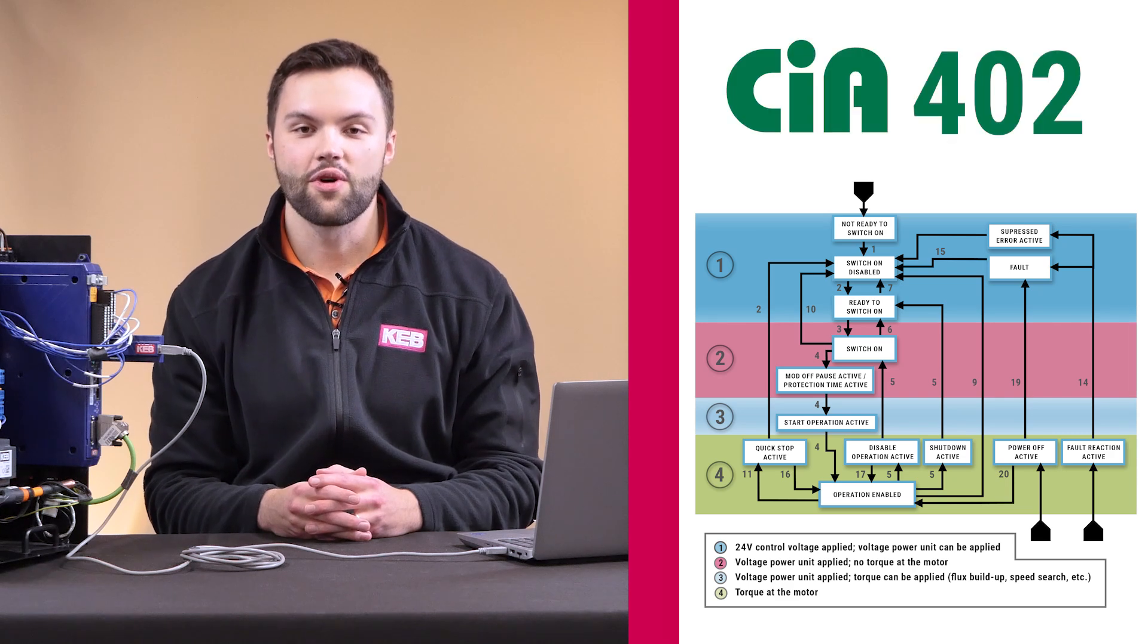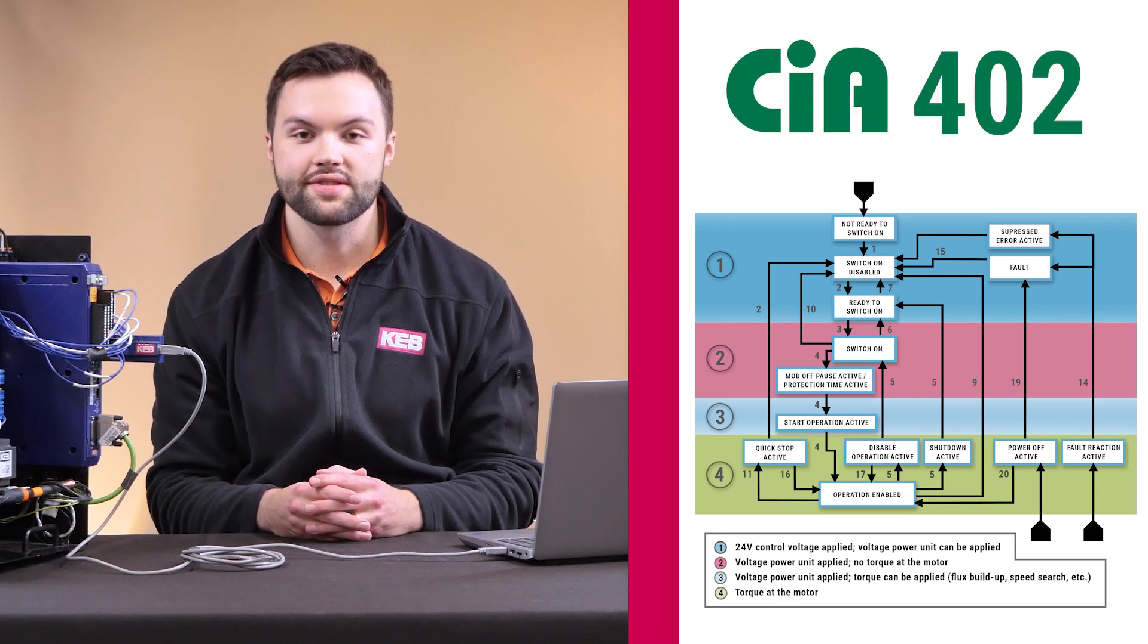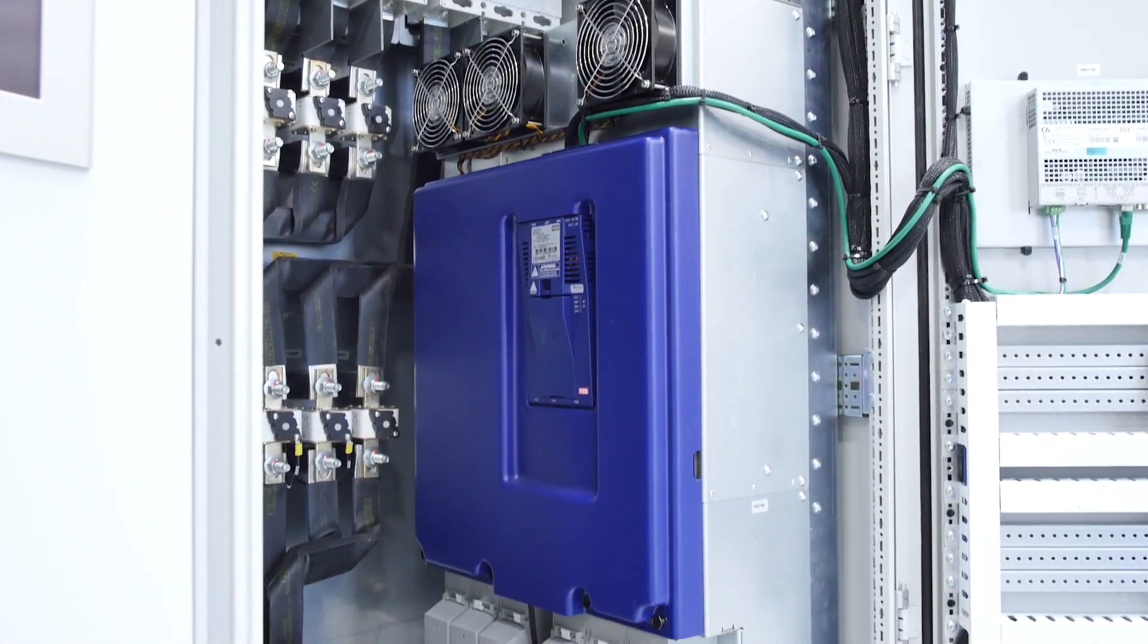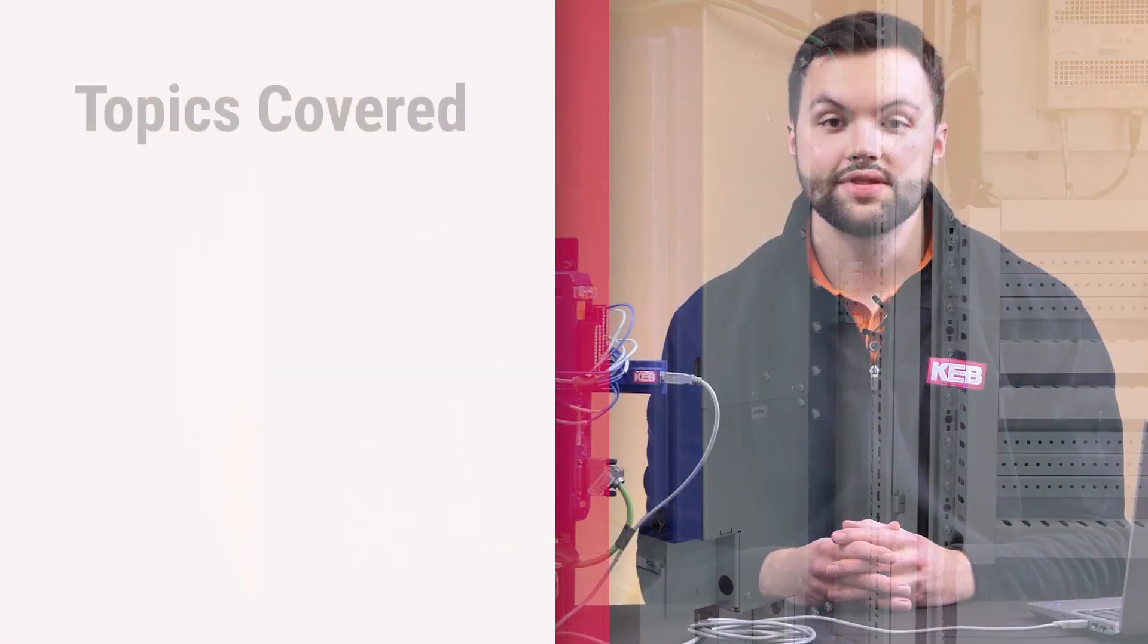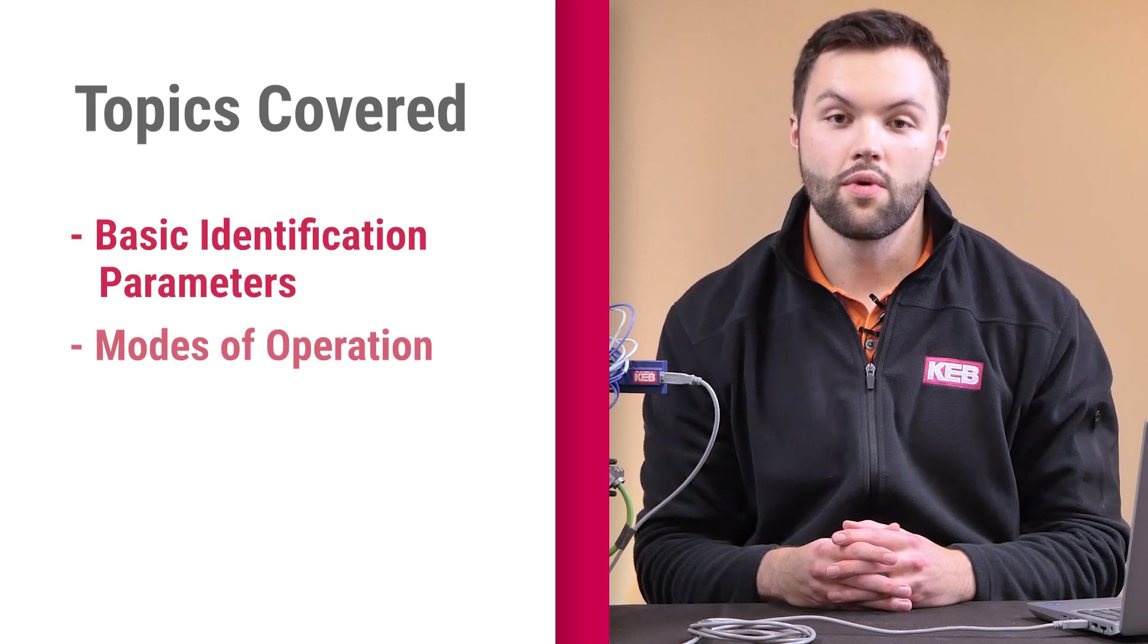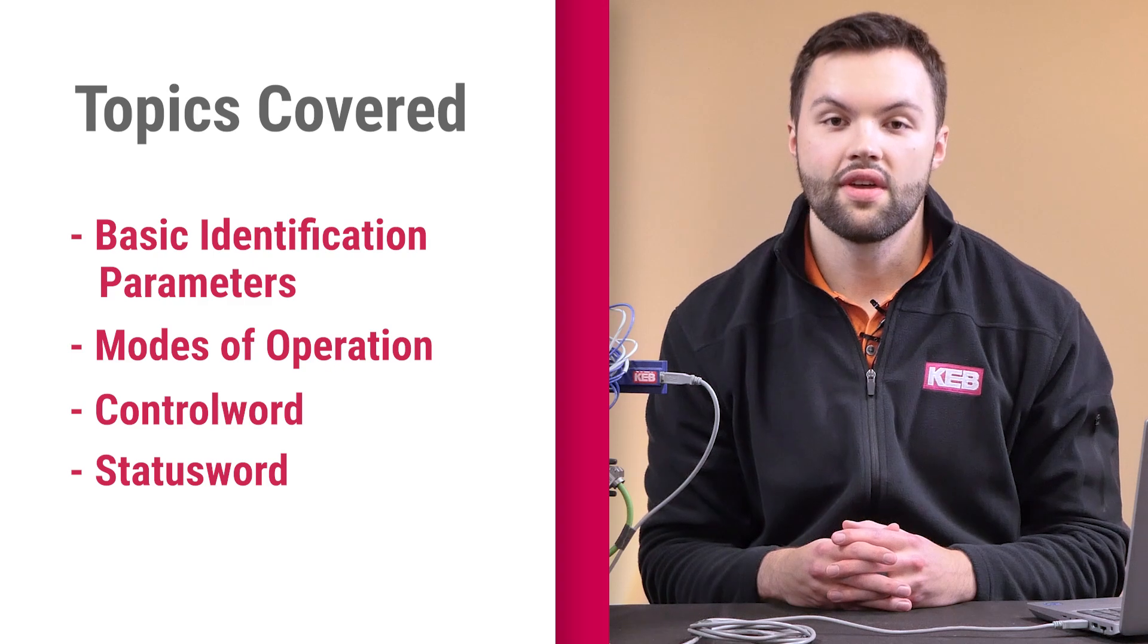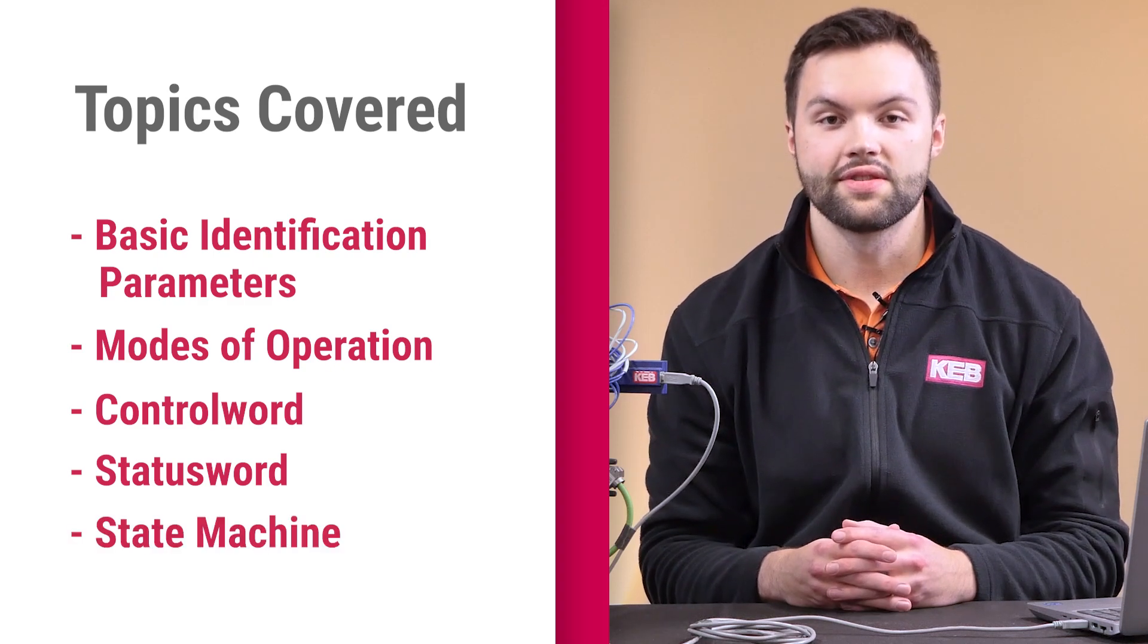The CIA402 profile is designed to standardize the control process for motor controlling devices, specifically variable frequency drives. This includes the basic identification parameters, modes of operation, the control word, the status word, and the state machine. We will overview all of these in this video.